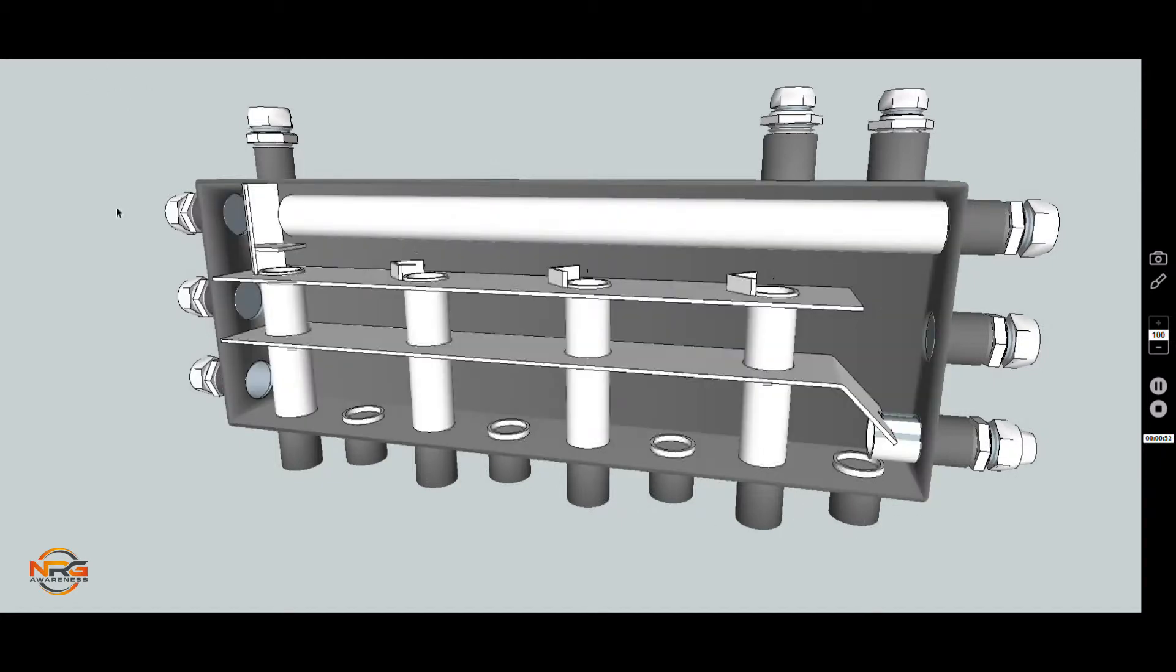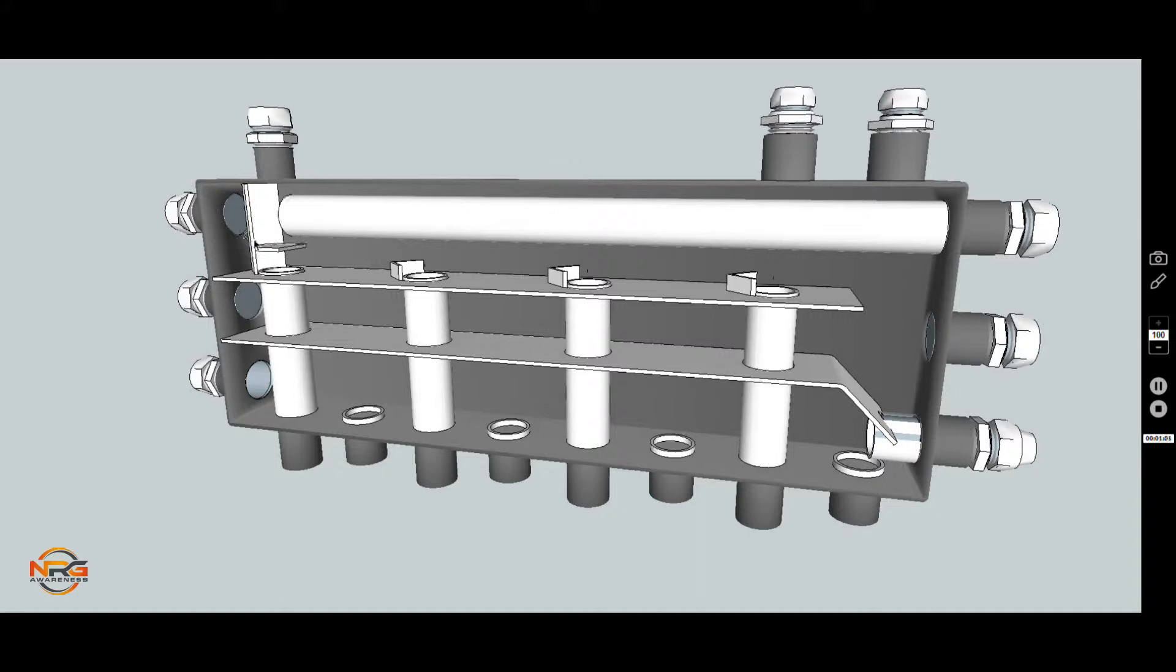The potential for a flow to come in here, water would bypass around this deflector plate, behind it and in front of it, travel beyond the zones and offer itself to the zones. If there's a pump operating here or here, it can take the hottest water. Any surplus water would pass through and go back to wherever it came from, either here or here.